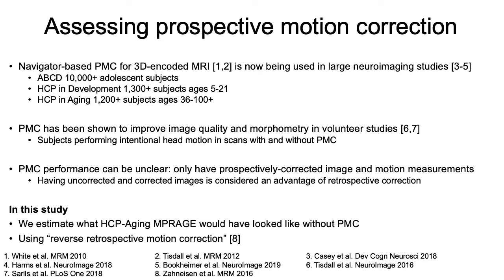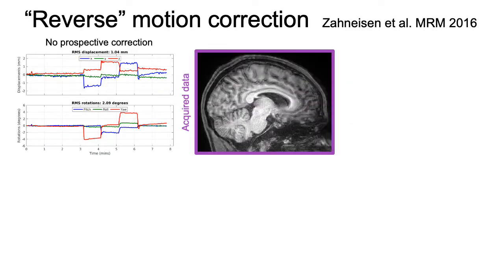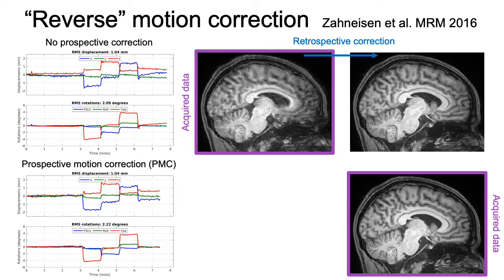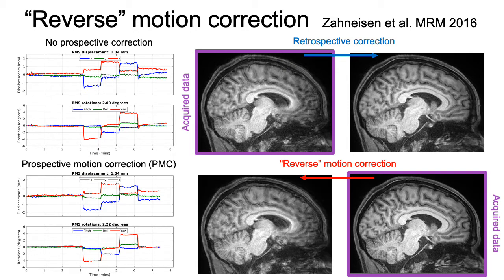In this study we estimate what the HCP aging MP-rage would have looked like without prospective correction, and we do this using reverse retrospective motion correction. Reverse motion correction was proposed by Zahneisen and colleagues a few years ago for 3D encoded sequences. In a prospectively corrected scan we can use reverse motion correction to go the other way and estimate what the image would have looked like without prospective correction.